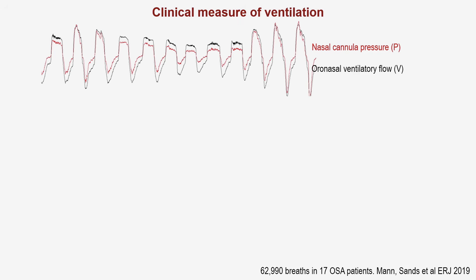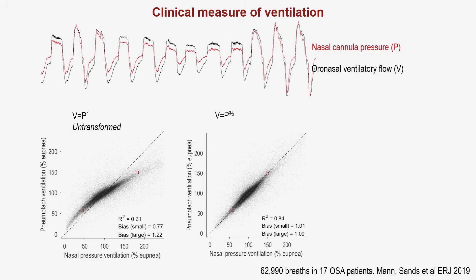But I wanted to show you what this looked like. We recorded nasal pressure and oral nasal ventilatory flow at the same time, and with all the caveats, if there's not too much mouth breathing, they track very nicely against each other, with the exception that respiratory events are a bit exaggerated in nasal pressure. So we've got this extra reduction in flow in nasal pressure. So whenever you see a 30% reduction in flow, that may not be an actual 30% reduction in real flow. It'll be a little shallower. So we transform this data. We take our nasal pressure signal, and instead of allowing this nonlinear, untransformed relationship, we transform nasal pressure with a power law function. We get closer to a line of identity and an absence of bias in terms of big breaths and small breaths.